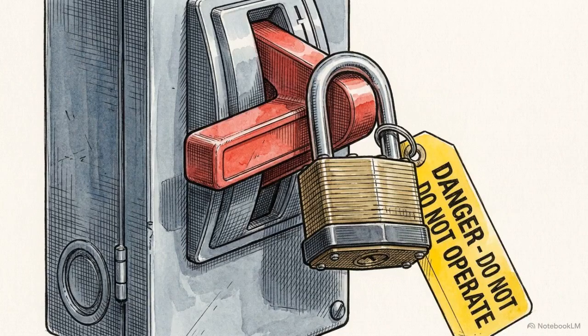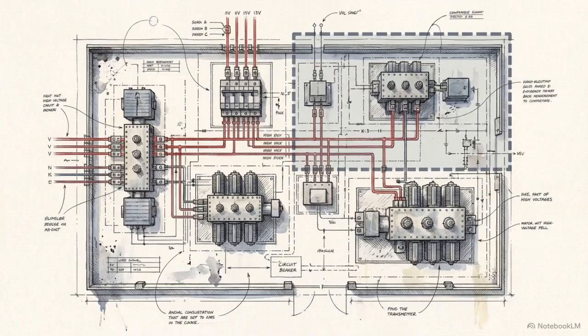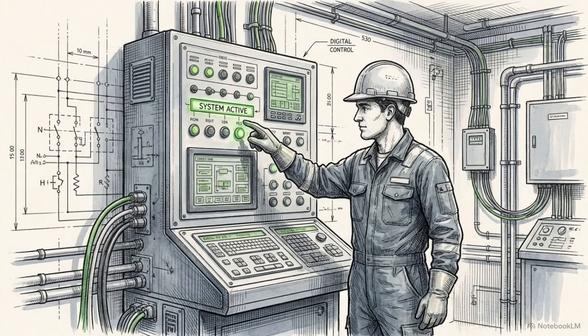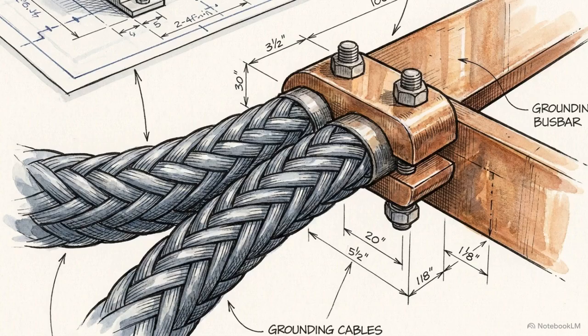Work begins with step 1 of the initial 8-step dead testing script, setting the LOTO boundary. The team reviews the switching order and applies safety warning tags to ensure the bank remains isolated from the grid. Step 2 requires verifying the final isolated and discharge status of every capacitor unit. This confirms the absence of stored energy before personnel handle the equipment.